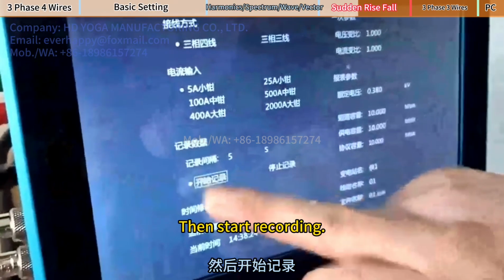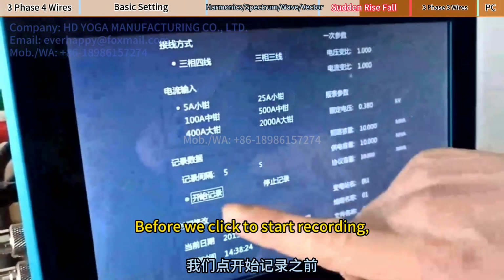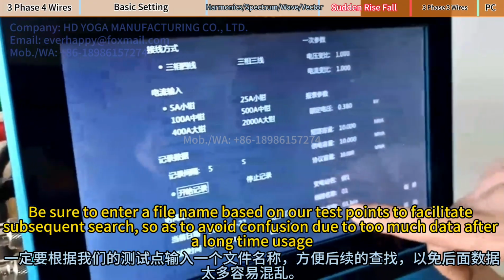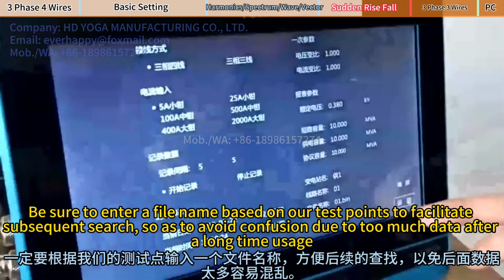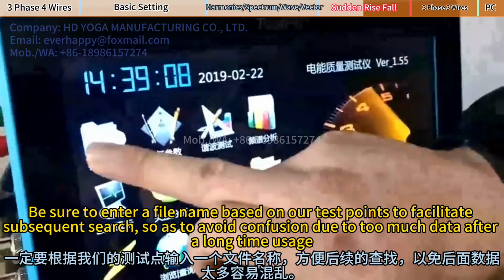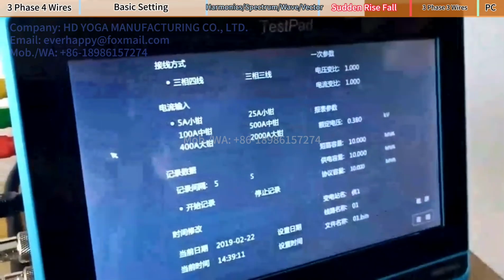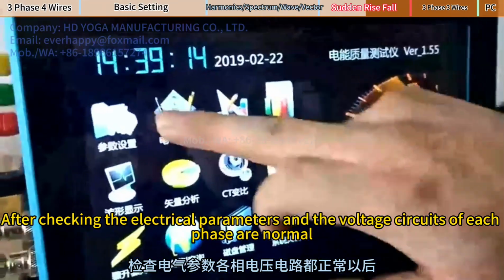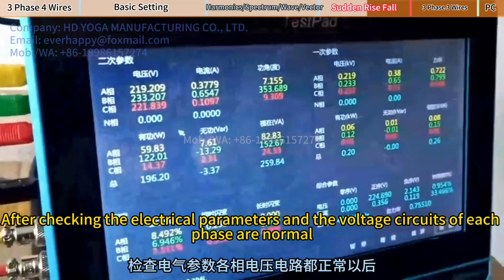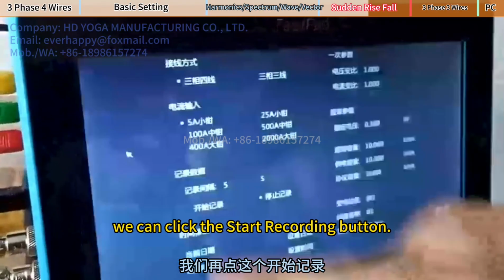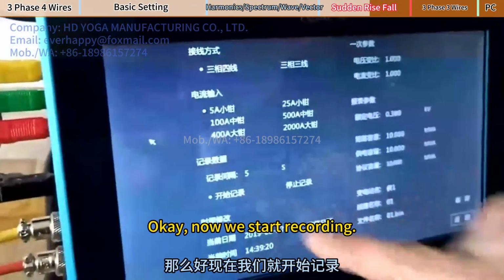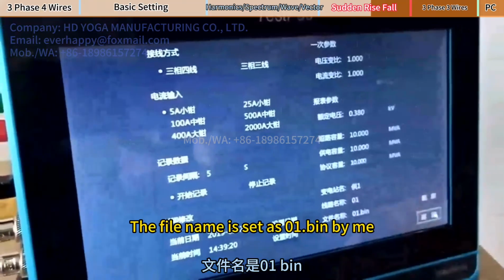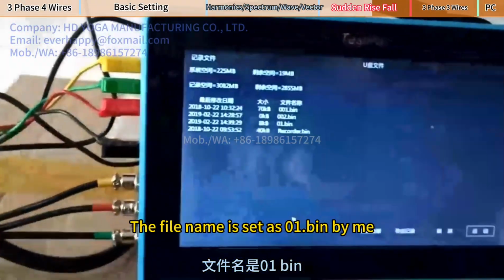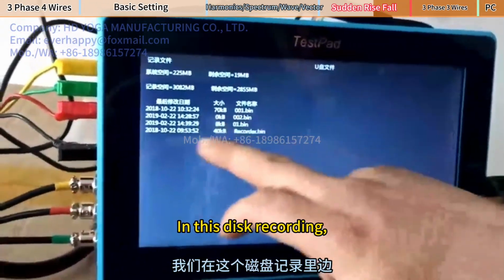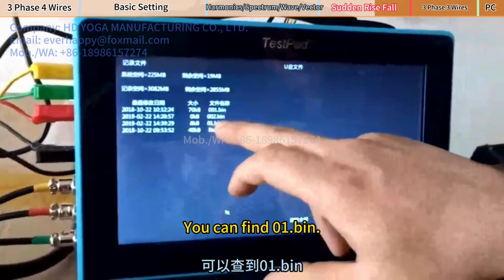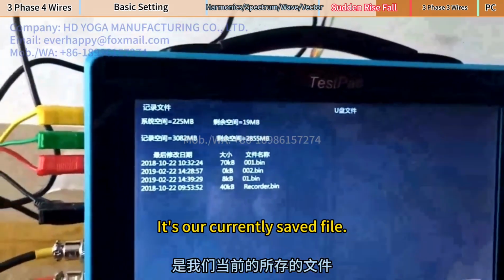Then start recording. Before we click to start recording, be sure to enter a file name based on our test points to facilitate subsequent search, so as to avoid confusion due to too much data after a long time usage. After checking the electrical parameters and the voltage circuits of each phase are normal, we can click the start recording button. Okay, now we start recording. The file name is set as 01.bin by me. In this disk recording, you can find 01.bin. It's our currently saved file.